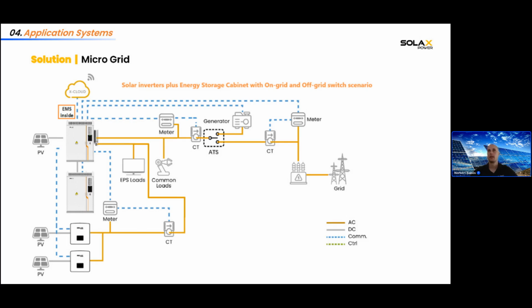And the third solution is the microgrid solution. So that's what I mentioned. If you have an old inverter system or string inverters and you would like to use this energy to supply your load or feed electricity back to the grid, you can connect these string inverters to the inverter's EPS side. And then even if you have an off-grid solution or a grid outage, it will switch to EPS mode. In this case, you will need to use two separate meters with their own CTs. The first one would monitor the grid, whether it has electricity or not. And the second one is to monitor the microgrid PV generation.